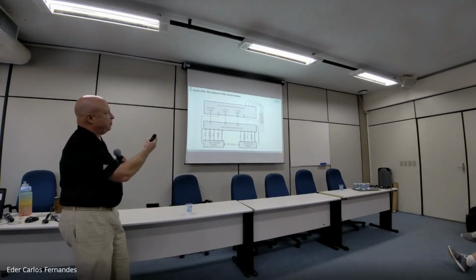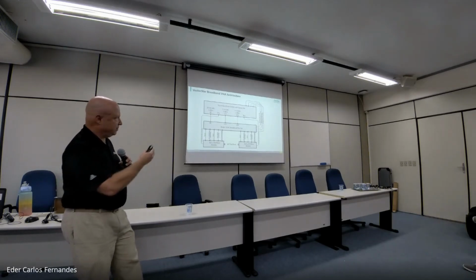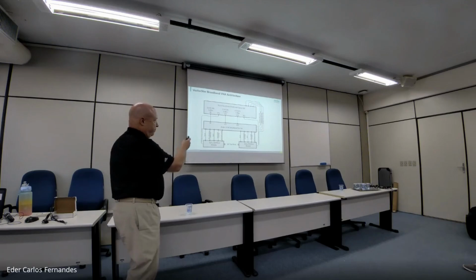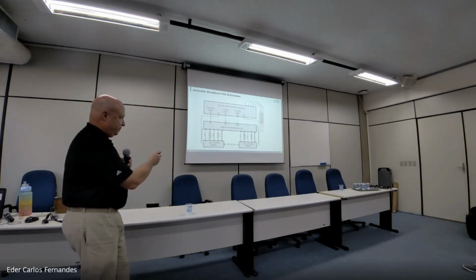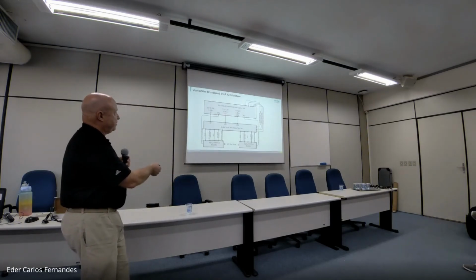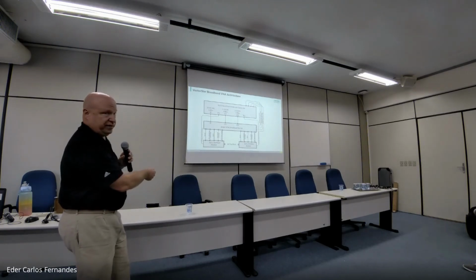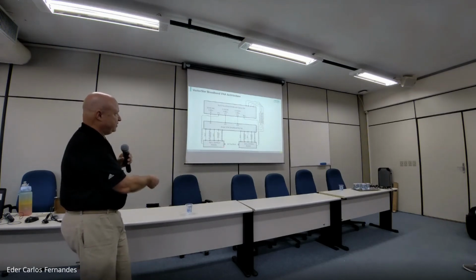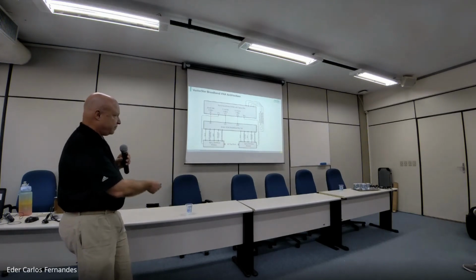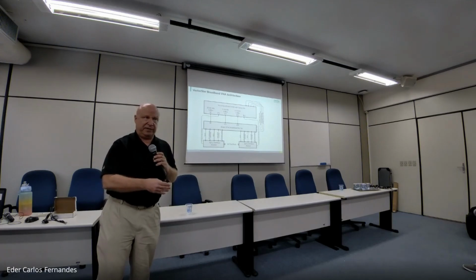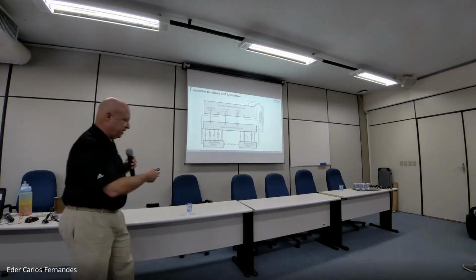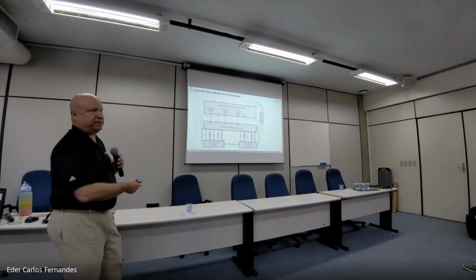This is just to show you what the different signals are interconnecting between the mainframe VNA, the top unit here. We have to supply the LO to the receiver inside the two modules. There's two separate LOs, one for each side. There's an RF that's generated and gets multiplied up in the modules, and I'll show you that block diagram in a moment. But again, all of these signals that we need for the source and for the receiver are generated in the mainframe, and they're carried through the test set and conditioned.